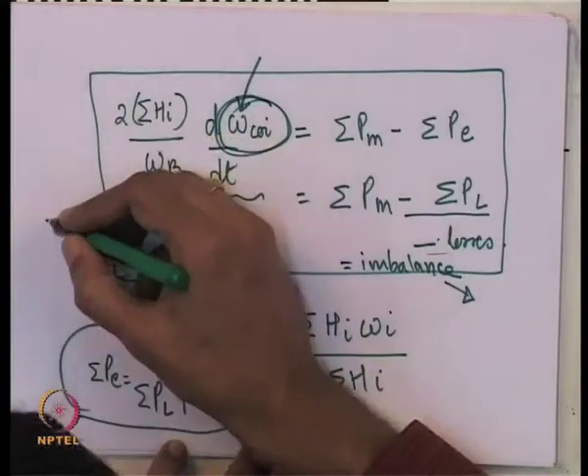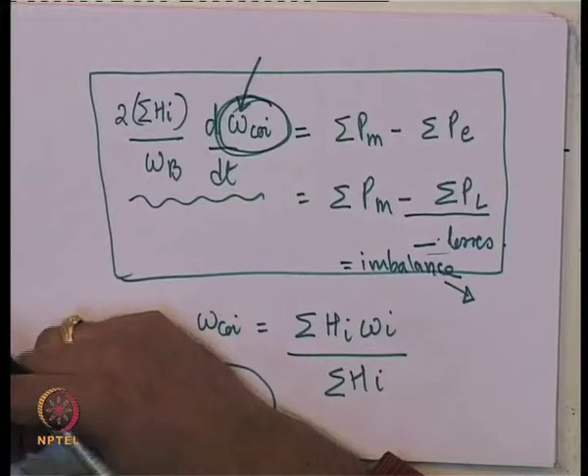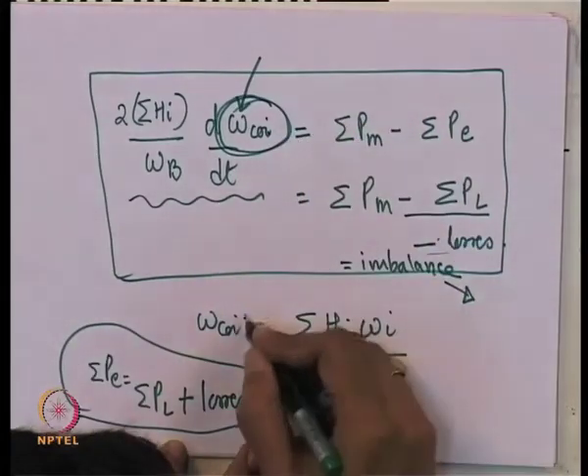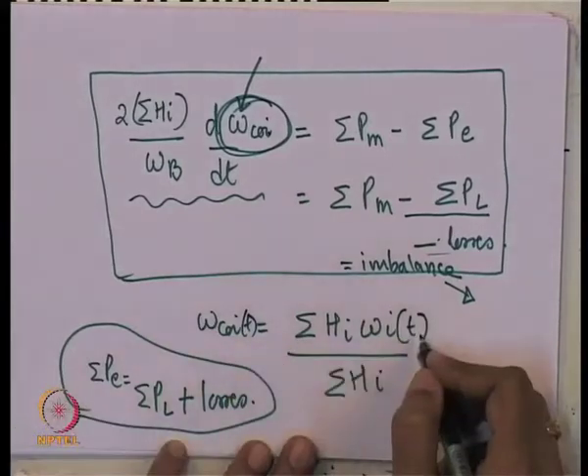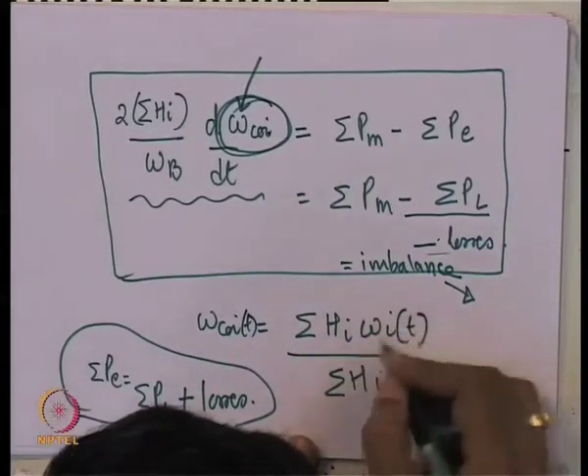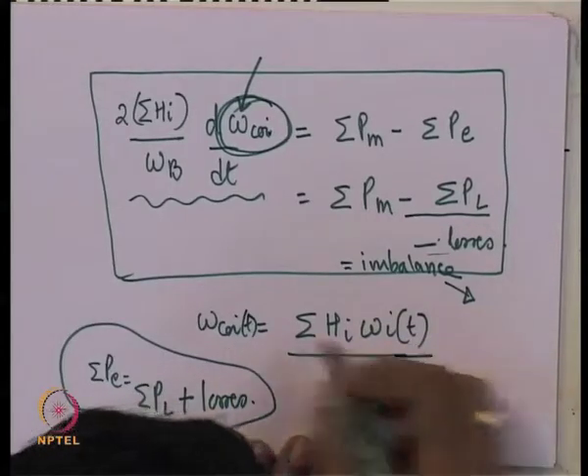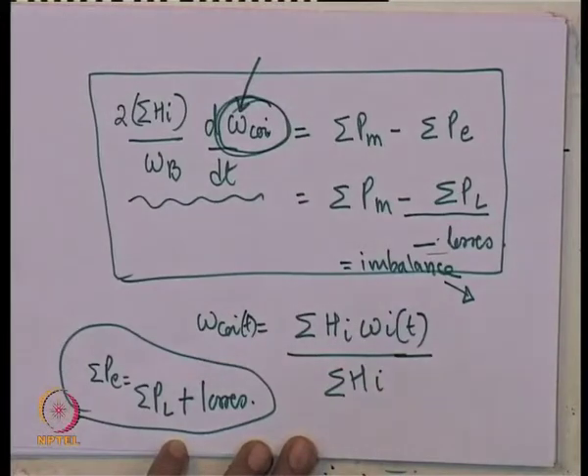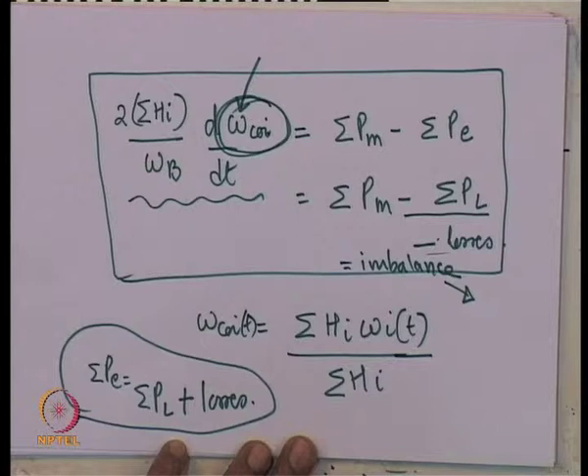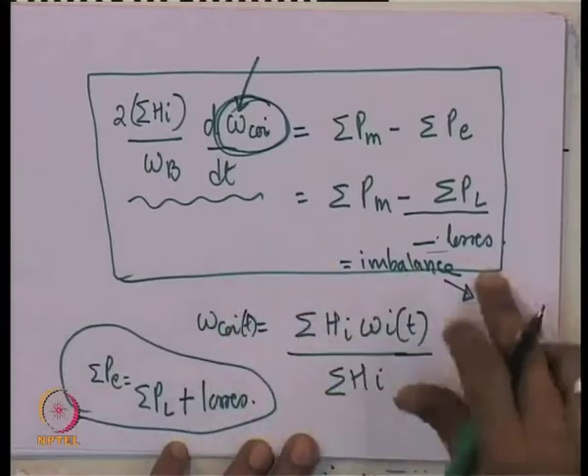The catch is that ω_COI is not a local signal — you must collect speeds of all generators, time-tag them, send them to a common point, compute the COI speed and estimate the load-generation imbalance, then choose a suitable chunk of load to trip. This is an interesting wide-area measurement scheme that is not currently implemented anywhere, but as engineers it is a conceptually feasible challenge using modern technology.